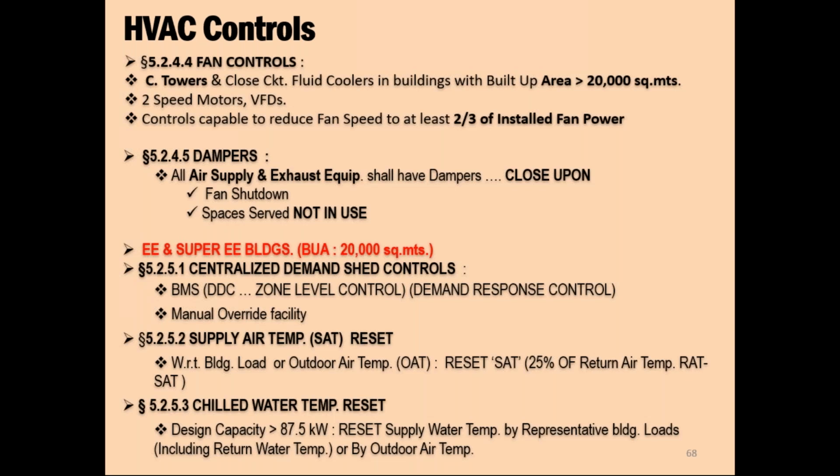Let me tell you something, operating chiller at higher temperature always gives you much more saving than controlling your AHU fan power or pump power. Because compressor has the largest motor, so typically a 100 TR machine will have about 75 kilowatt of motor, which will be operating or consuming about 55 to 60 kilowatt of power, typically at 0.59 or 0.6 kilowatt per TR.